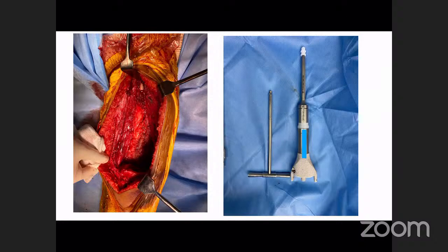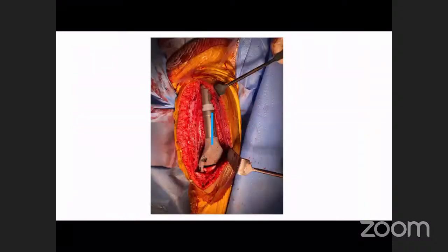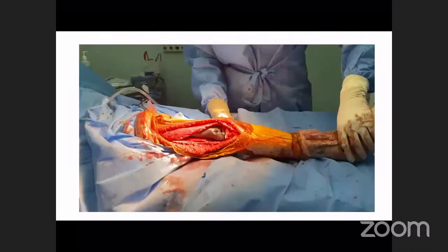That's why, for the design of the fixation, you should not have too long a stem, plate, or intermediary cutting fin. That gives you a very big difficulty reducing the two fragments together. So normally we will take about 1 cm for the cutting fin or any intermediary part, so that we can pull the soft tissue and reduce it.